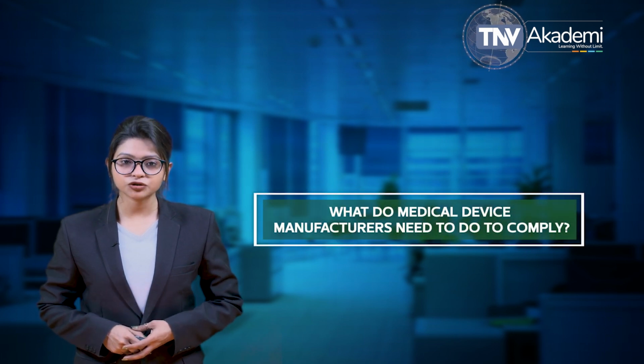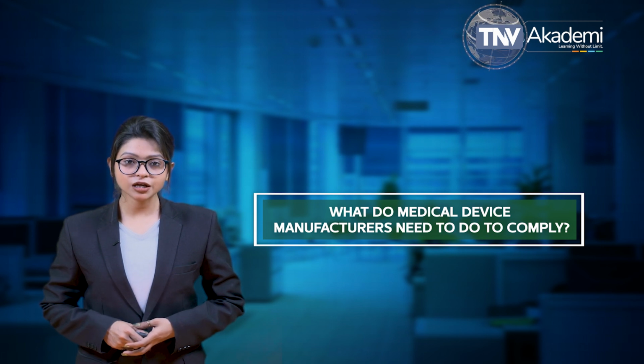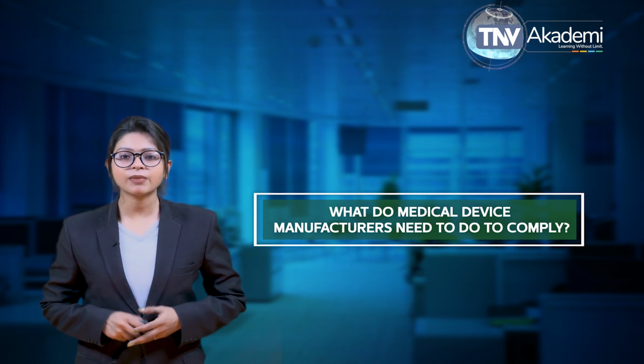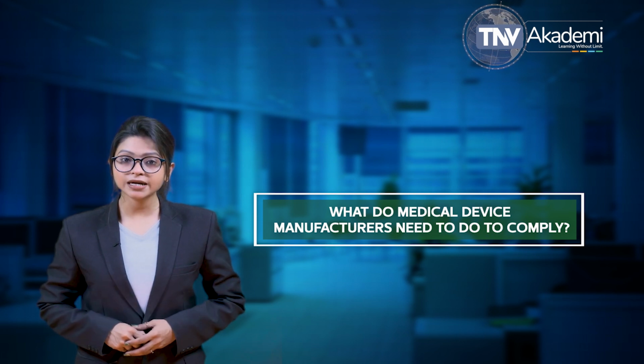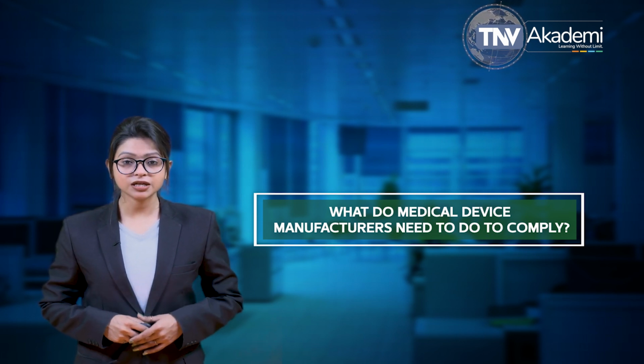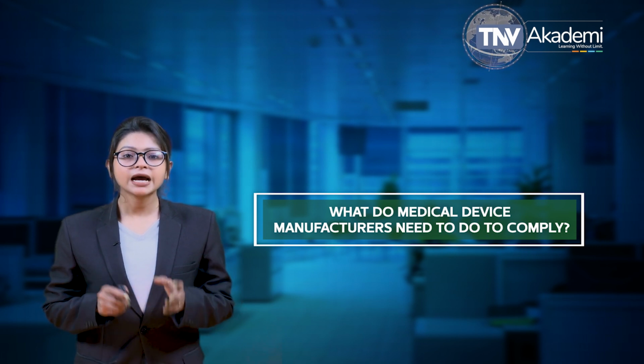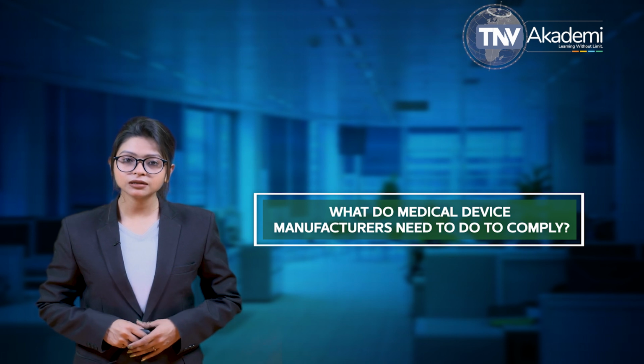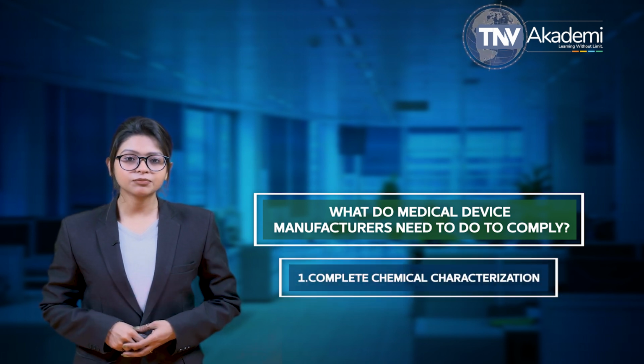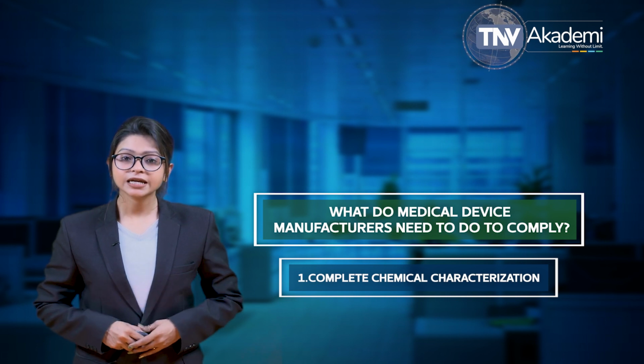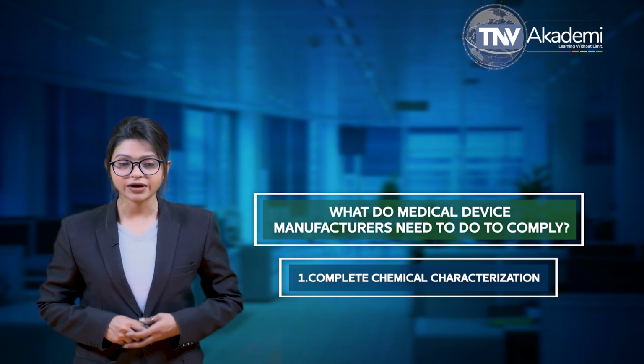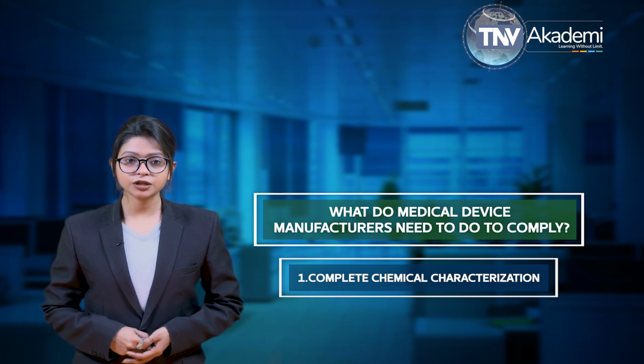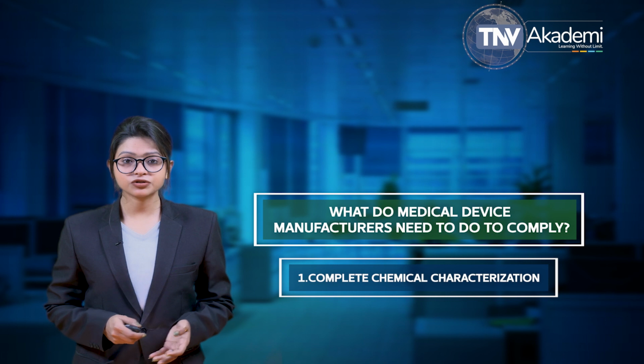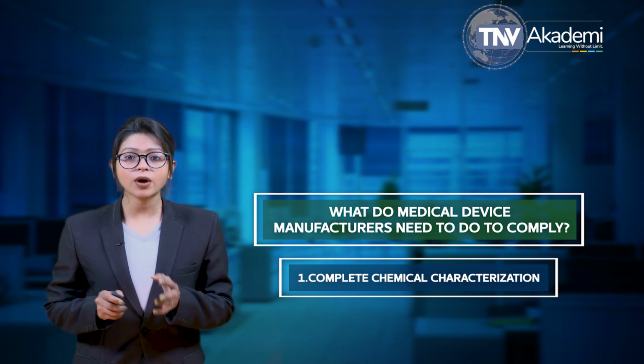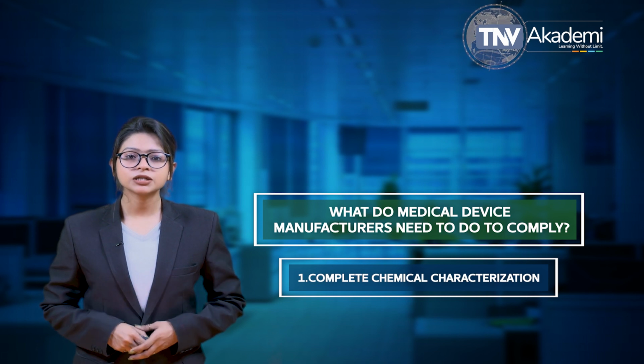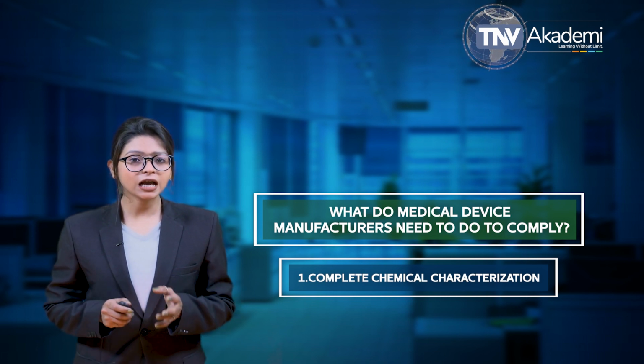What do medical device manufacturers need to do to comply? There are generally three phases involved in evaluating biological risk as a part of a biological evaluation under ISO 10993-1: complete chemical characterization, toxicological risk assessment and biocompatibility testing, ideally in that order. The first one, complete chemical characterization, identifies the chemicals and the quantity of those chemicals per device. Additional data often needs to be generated through extractables and leachables (E&L) testing. E&L testing can provide sufficient data to address some biological endpoints, including genotoxicity and systemic toxicity, helping you avoid costly and time-consuming biological testing.